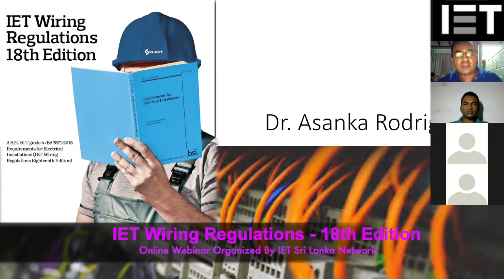Okay, thank you. And next question is, if we connect all earth to a single earth network, what is the minimum earth electrode resistance to be maintained? So the earth electrode resistance matters only if you have a TT system. In the TN system, the earth electrode actually doesn't matter. That's why the standard is silent on that one, because you have equipotential everywhere.